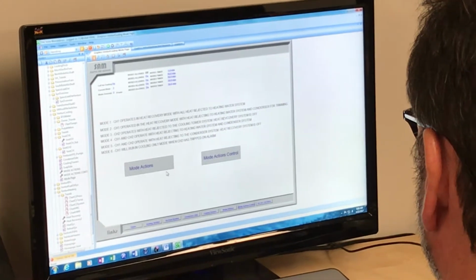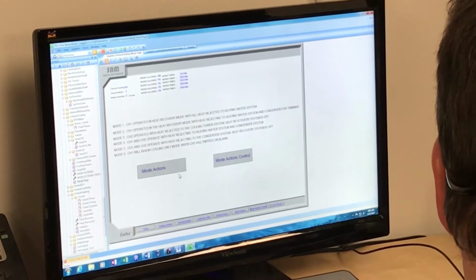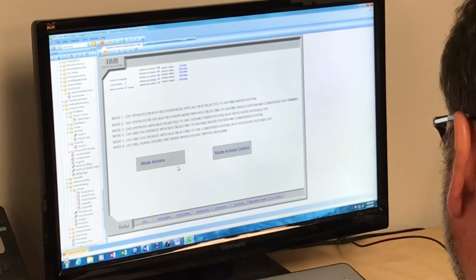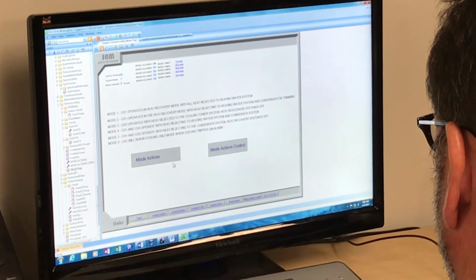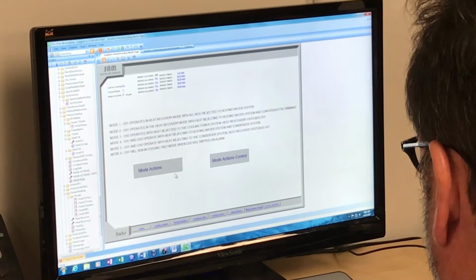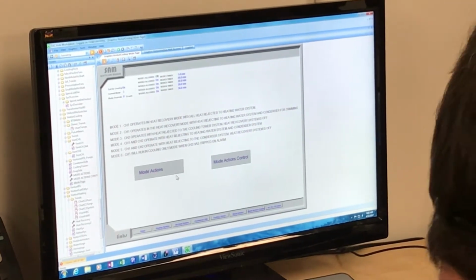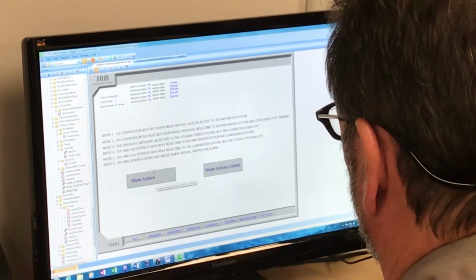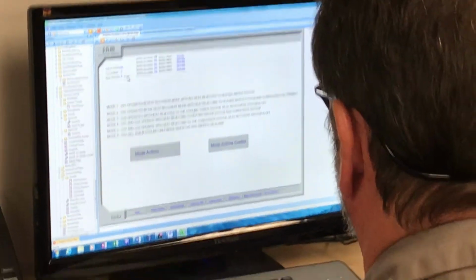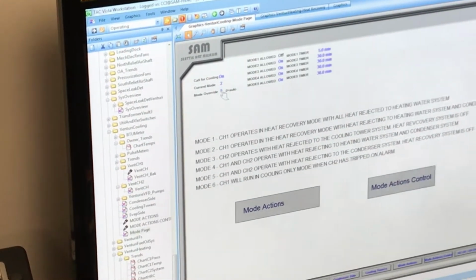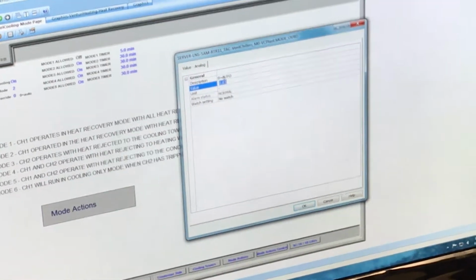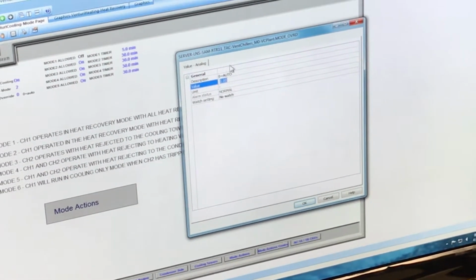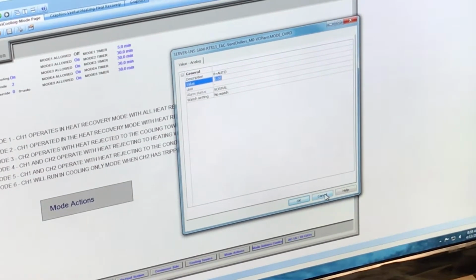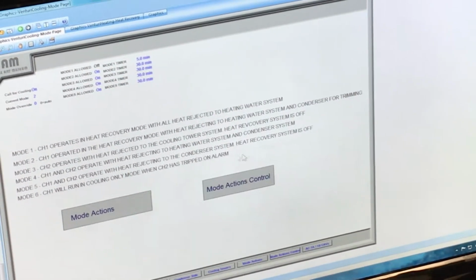Now, could you explain to him how, in an emergency situation, we would go from mode 2 to mode 3? How would you go about that if we're only in mode 2 right now? Well, there are 2 ways to do it. You can override it, for one. There is a mode override here, where 0 is auto, and you're familiar with overriding. You just write the mode that you want it to go in. You don't need to force the set point. It's just a force, but it'll change modes that way.